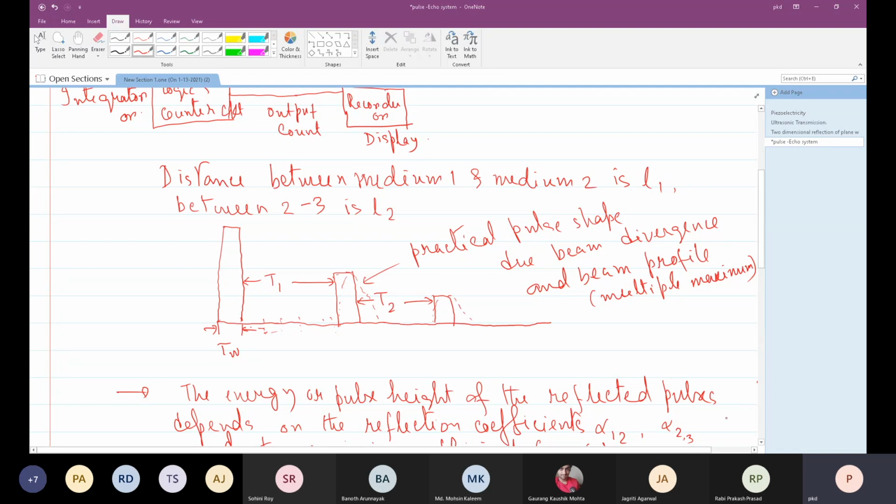Often this measurement is carried out over multiple pulses. One pulse is launched and then we get certain energy here. That is usually done with integrators. There are gating times for the integrators, and multiple integrators corresponding to how many discontinuities the equipment can detect. The first integrator will operate for this time.